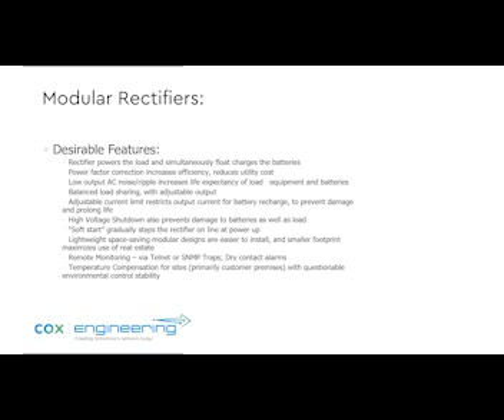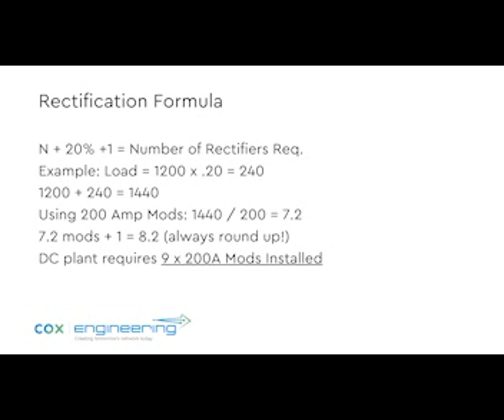So if you're looking at rectifiers, one thing you want to do is take N, which is the number that you actually need based on the load, and then add 20%, generally for battery recharge, and then add 1 for N+1. So for example, if you have a load of 1200 amps and you take 20% of that, which is 240 amps, this is all DC, you add it to the 1200 and it's 1440. If you're using 200 amp modules, you divide that 1440 by 200, and we need 7.2. Obviously you're going to round up, so that's 8, and then you add 1 for redundancy, so that's 9.